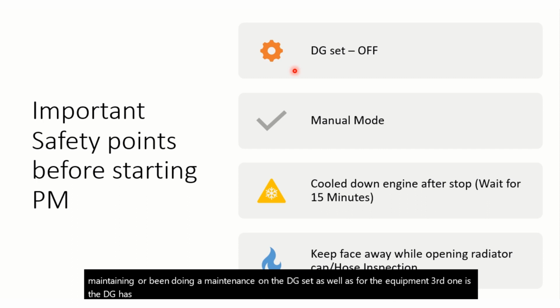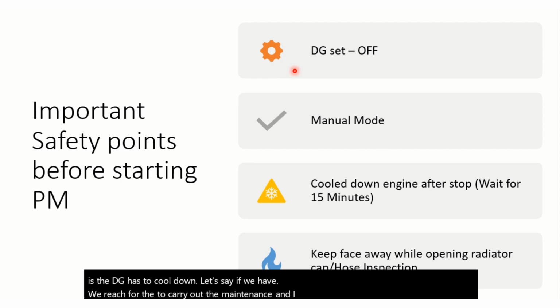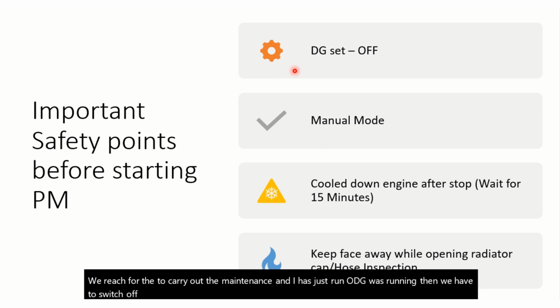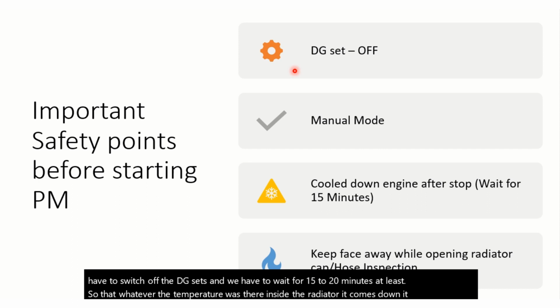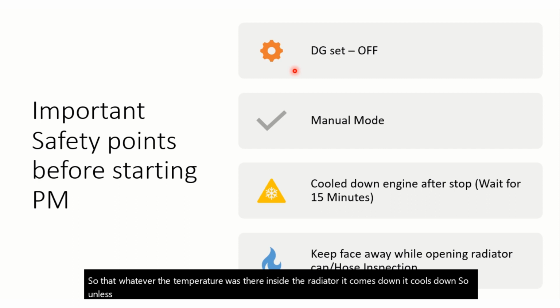Let's say we reach to carry out the maintenance and the DG has just run, or the DG was running. Then we have to switch off the DG sets, and we have to wait for 15 to 20 minutes at least, so that whatever the temperature was inside the radiator comes down, it cools down. Unless and until it has cooled down, we should not start our preventive maintenance. So this is a very important check.